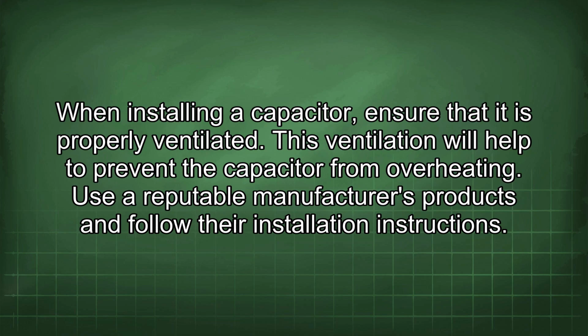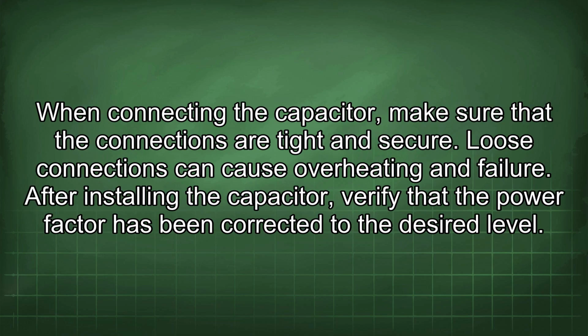When installing a capacitor, ensure that it is properly ventilated. This ventilation will help to prevent the capacitor from overheating. Use a reputable manufacturer's products and follow their installation instructions. When connecting the capacitor, make sure that the connections are tight and secure. Loose connections can cause overheating and failure.